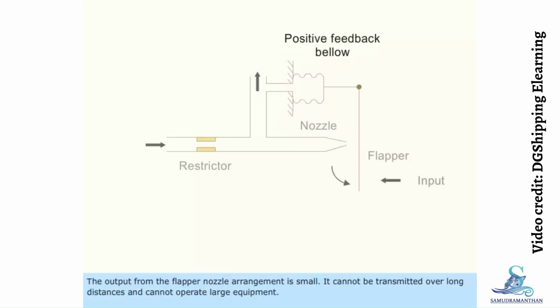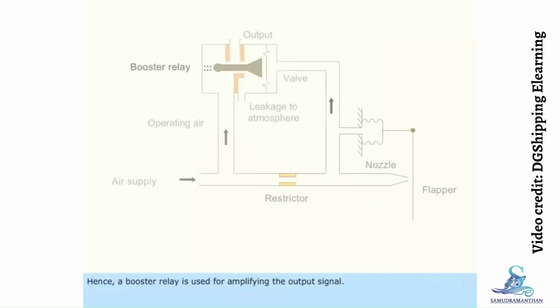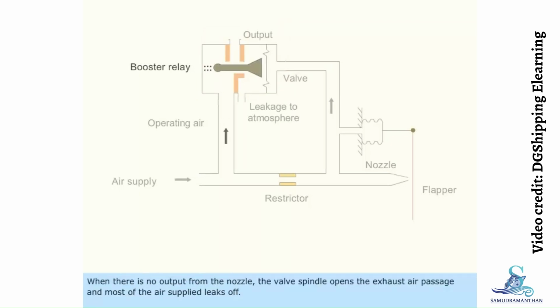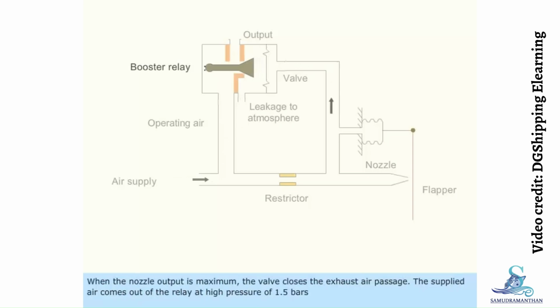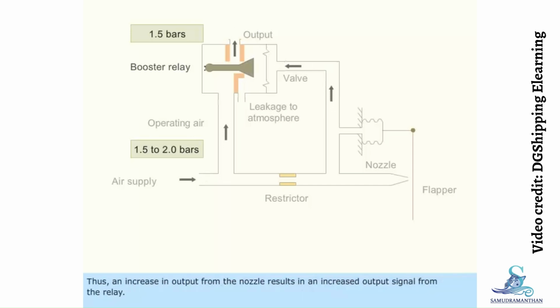The output from the flapper-nozzle arrangement is small. It cannot be transmitted over long distances and cannot operate large equipment. Hence, a booster relay is used for amplifying the output signal. Air is supplied to the booster relay. When there is no output from the nozzle, the valve spindle opens the exhaust air passage and most of the air supplied leaks off. When the nozzle output is maximum, the valve closes the exhaust air passage. The supplied air comes out of the relay at high pressure of 1.5 bars. Thus, an increase in output from the nozzle results in an increased output signal from the relay.